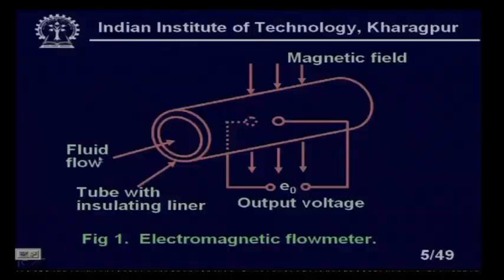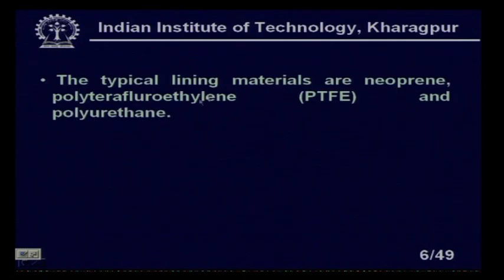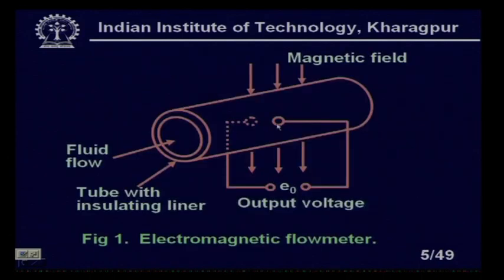The line connecting the two electrodes and the direction of the magnetic field and the flow direction are all mutually perpendicular to each other. The fluid flows through the pipe with the insulating liner. We produce the magnetic field with proper coils, and two sensors are installed on diametrically opposite sides. The output voltage is calibrated in terms of flow.